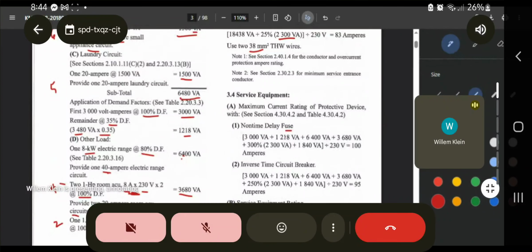So for the fuse, you get the total of the loads, but for your highest rated motor, you'll use 300% multiplier. And then divided by 230 volts, so you get here 100 amperes. For the circuit breaker, same computation except that your highest rated motor will use 250% multiplier. Okay, so the rest of the loads, you just add. Okay, but when you're adding your highest rated motor, you will use a multiplier of 250% for the circuit breaker. So they computed here 95 amperes.